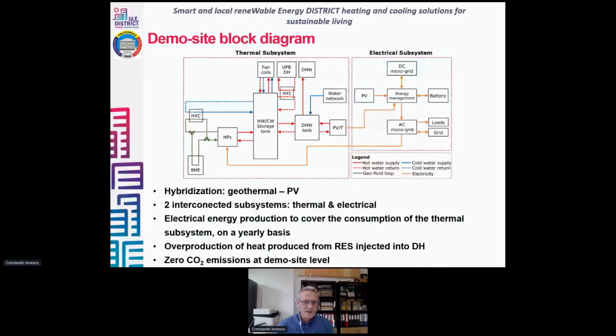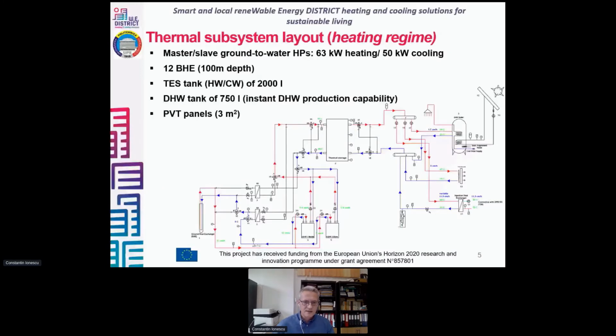Here we have the final layout of the thermal subsystem. It is based on two heat pumps with a total heating power of around 63 kilowatts and cooling power of 50 kilowatts. They work in a master-slave configuration. The heat pumps are of ground-to-water type, using energy extracted from the ground by means of a borehole heat exchanger composed of 12 geothermal probes.